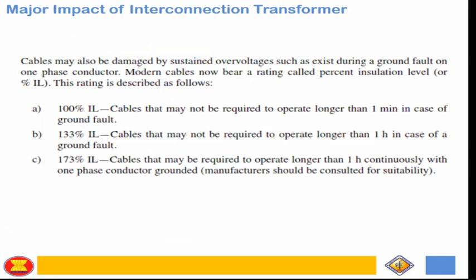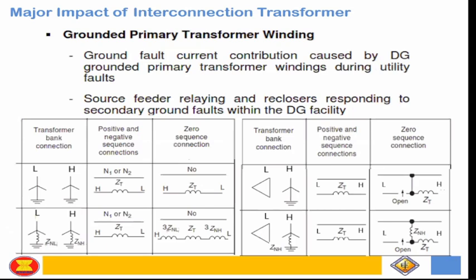But the worst case, if you are the designer, if your system is ungrounded, you need to consider to improve, no, the insulation level up to maybe 133%, or the safest one is 173%. Okay, so that's for the design consideration for ungrounded system. And what about, no, the grounded primary transformer winding? What's the impact? Okay, so sabi dito, ground fault current contribution caused by DG, no, grounded primary transformer windings during utility faults. Okay, and then source feeder relaying and reclosing responding to secondary ground within the DG facility.